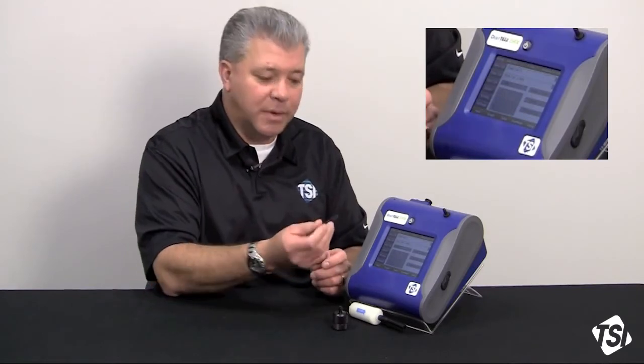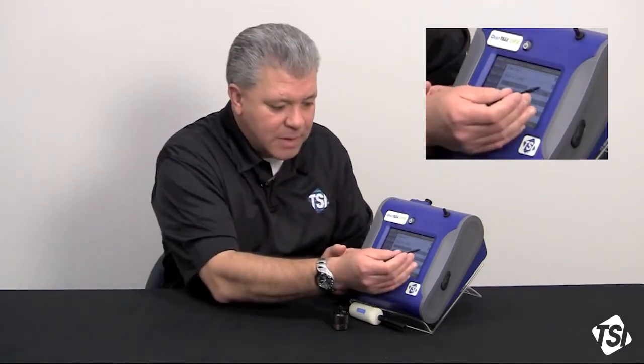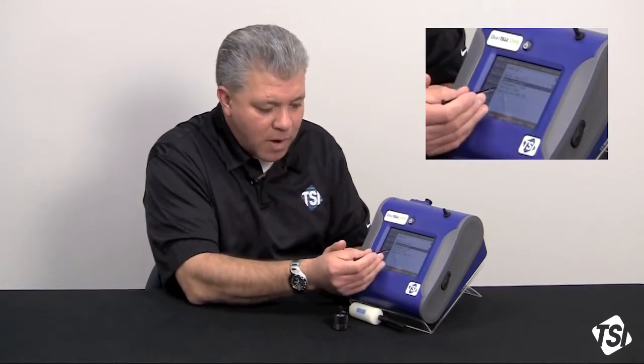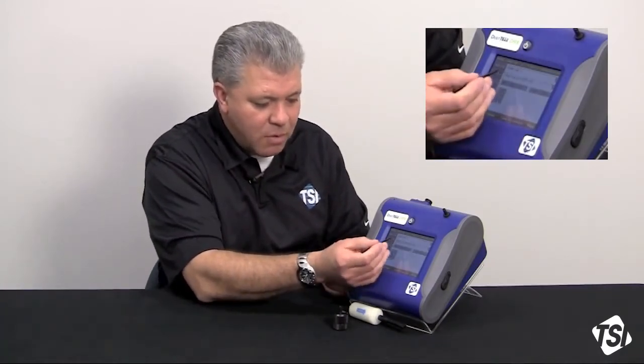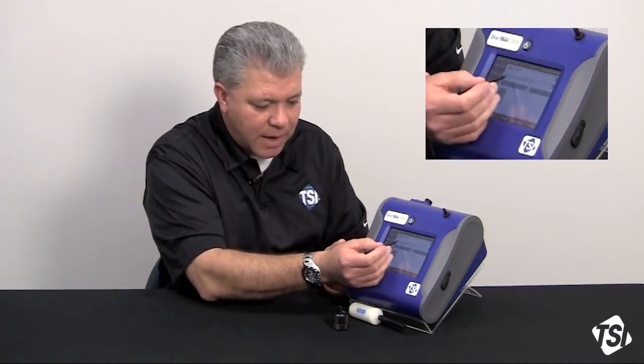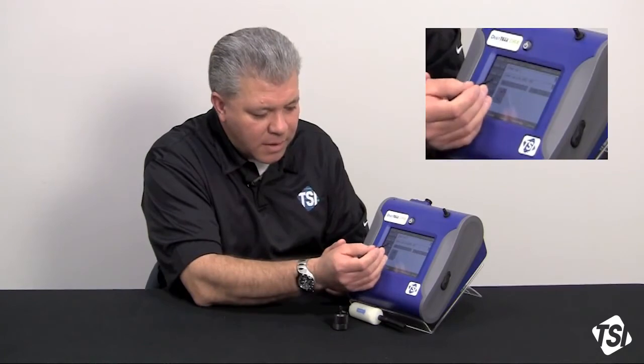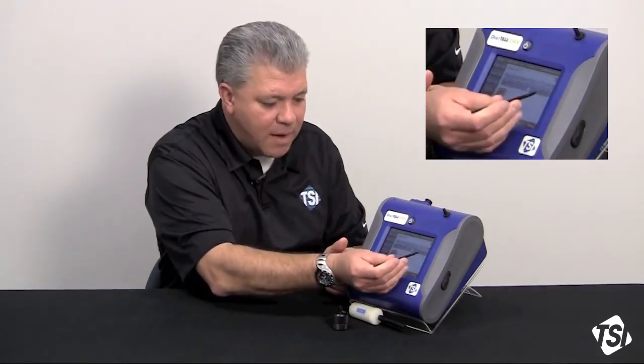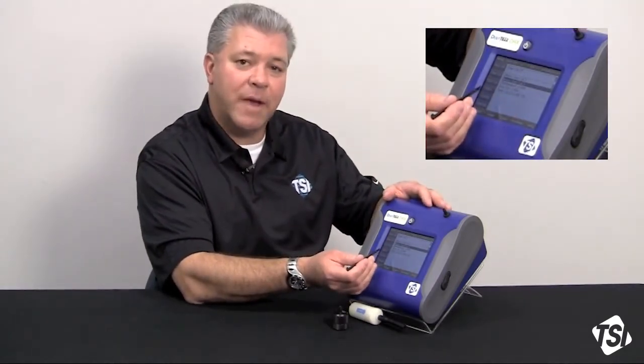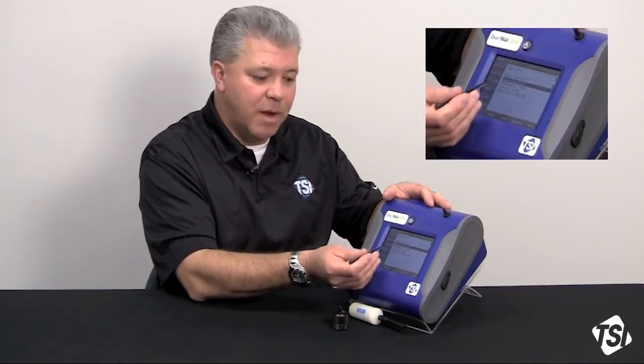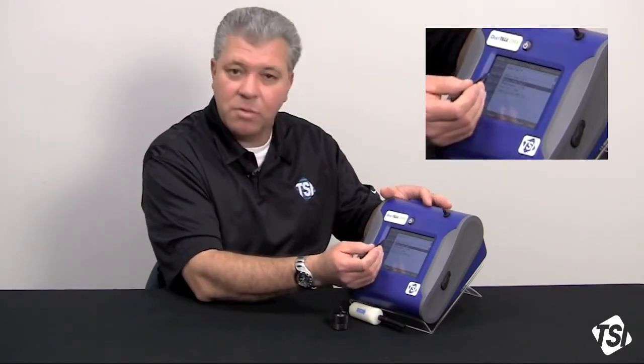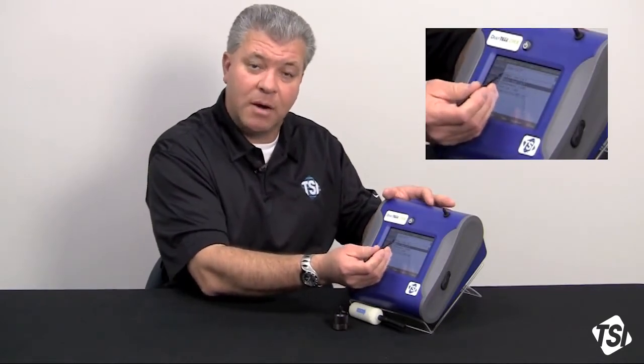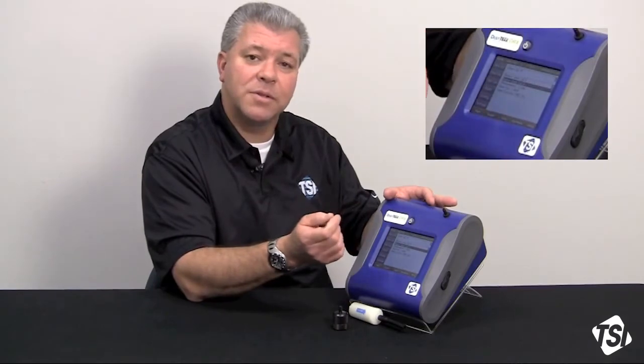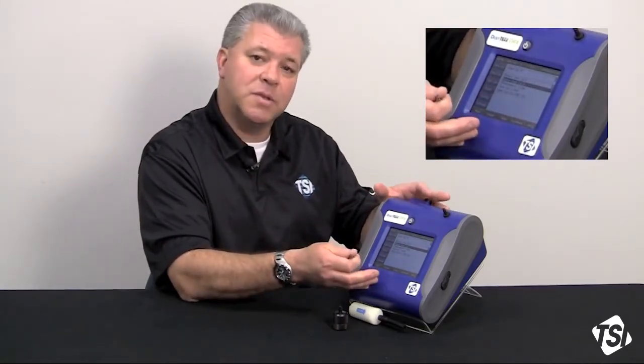Let's say that your new cal factor came back at 1.40. You would definitely want to accept that, save that new number, and then enable that user cal. On this bottom row here, it'll say user cal off, and what you want to do is toggle it so that it is on, and then you save that. Now this user calibration, with this new real-time size correction factor that you just did, is input into the instrument. This is going to be the new correction factor, so it would be 1.4, for example, for size correction factor, and your photometric correction factor is still 1.0, but that is what the instrument is now going to run at.